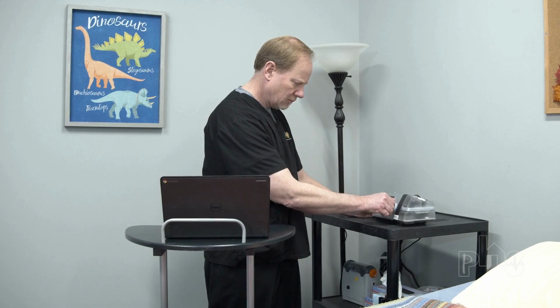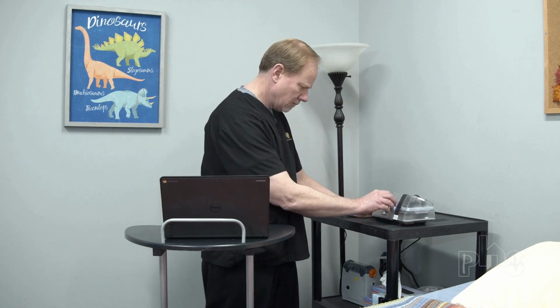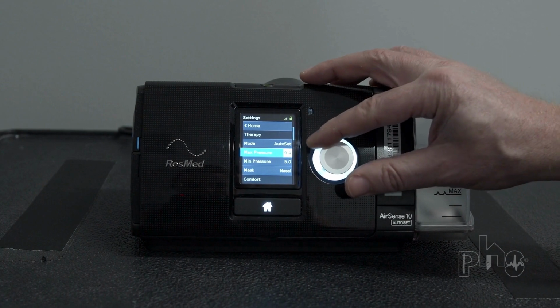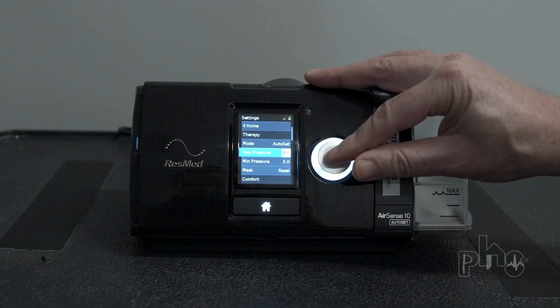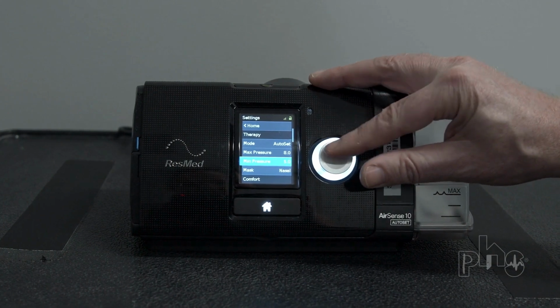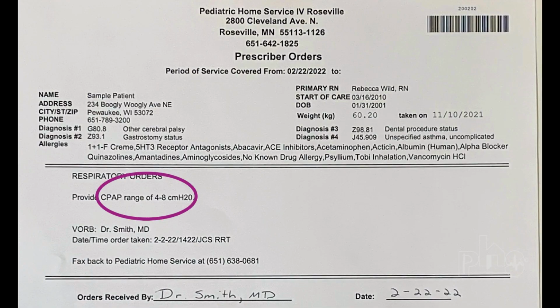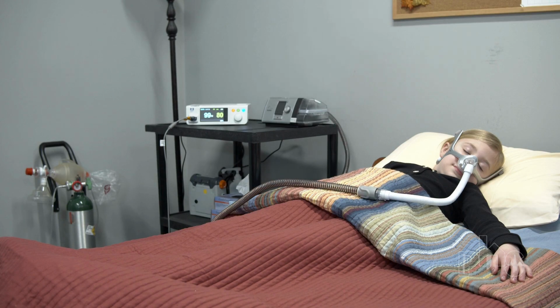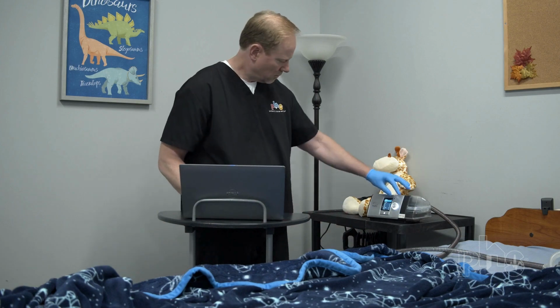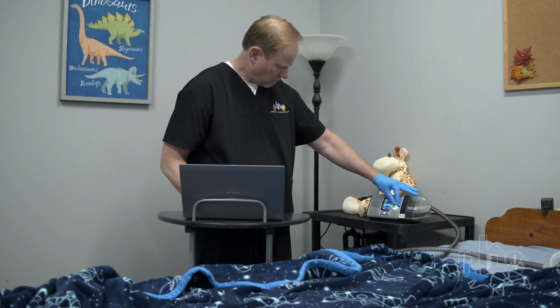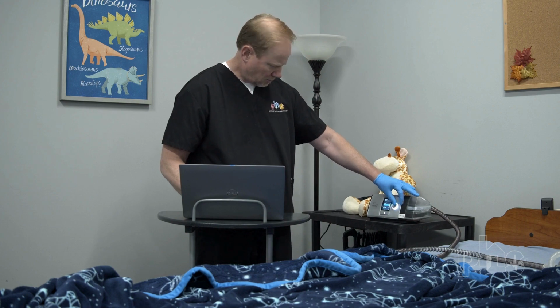There are also auto-adjusting CPAP and BiPAP machines. Instead of static pressures, these machines can be programmed with a range of pressures. For example, a patient with an auto-adjusting CPAP machine may have a prescription for a CPAP range of 4 to 8 centimeters of water. The auto-adjusting CPAP machine adjusts within that range to find the best pressure to keep the patient's airway open. Auto-adjusting BiPAP machines can also be programmed to automatically adjust during therapy to best ventilate the patient. Respiratory clinicians set up CPAP and BiPAP systems for patients based on their prescription and may program additional settings based on patient needs.